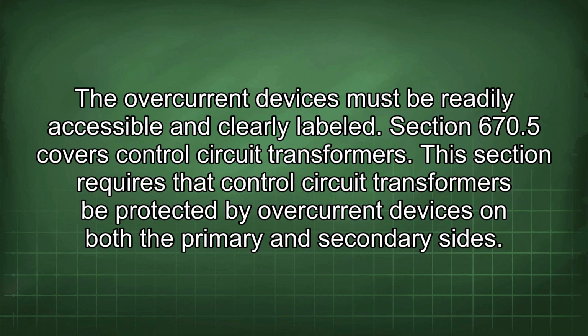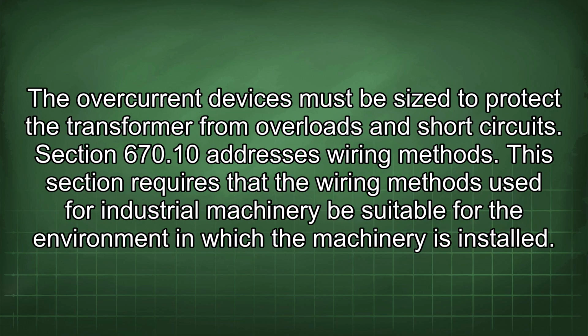Section 670.5 covers control circuit transformers. This section requires that control circuit transformers be protected by overcurrent devices on both the primary and secondary sides. The overcurrent devices must be sized to protect the transformer from overloads and short circuits.